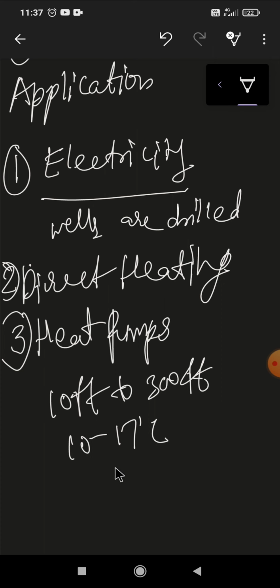A geothermal heat pump system consists of a heat pump, an air delivery system, ductwork, a heat exchanger, and a system of pipes buried under a landscape area, parking plot, or any number of areas around the building. In winter, the heat pump removes heat from the heat exchanger and buried pipes and transfers it into the indoor air delivery system. In summer, the process is reversed, and the heat pump moves heat from indoor air and delivers it to the heat exchanger.